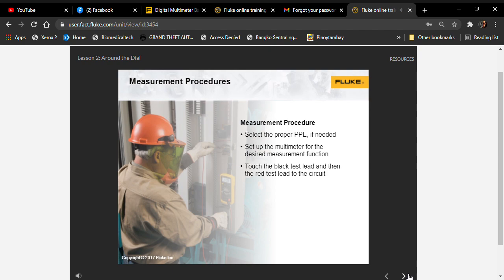Best practice is to connect the black lead first and then the red lead. Then read the measurement from the multimeter display. Be sure to note the decimal point and units. Finally, you disconnect the test leads, starting with the red one, followed by the black one.